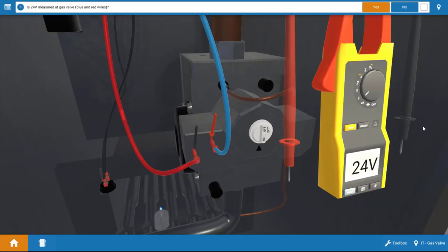And again, this verifies that all our safety switches are closed, and the gas valve is in fact receiving 24 volts. So we're going to click yes up here.